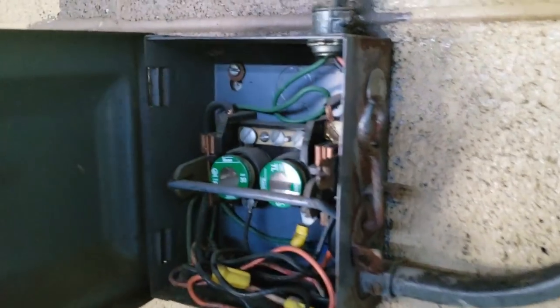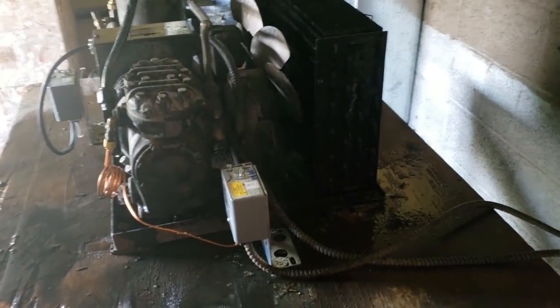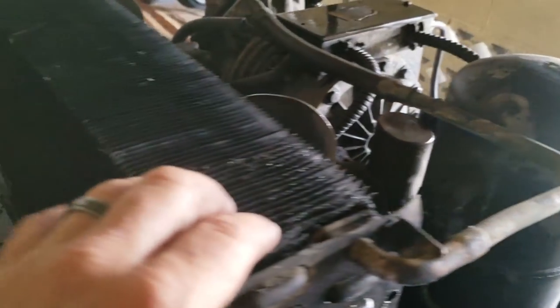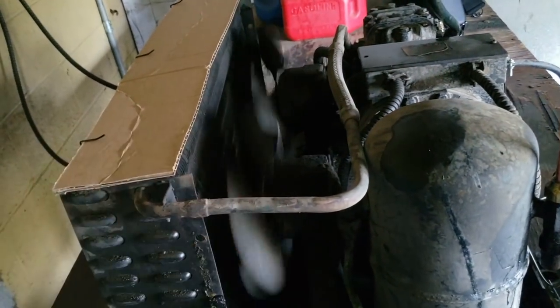I always like to make sure the fork's got all the way in there, and then double-check those fuses to make sure they're the right ratings. So we got that back in there, got our wash out done. That made a little bit of difference — it wasn't horrid, but you can definitely see through it now. A lot better. It probably wouldn't hurt to have a little piece of cardboard across the top. Cleaned that coil out and made a little difference because the fans have cycled on and off three times.